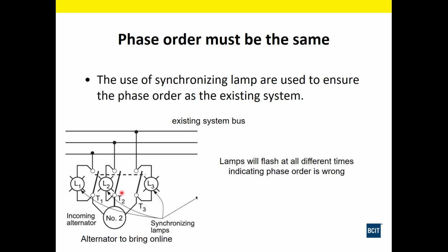But before that happens, if our phase order is out, these 3 lamps are going to be flashing. Now remember, if you remember the previous slide, we saw the different peaks of the frequency waveforms were not in phase. So imagine if that was A phase.